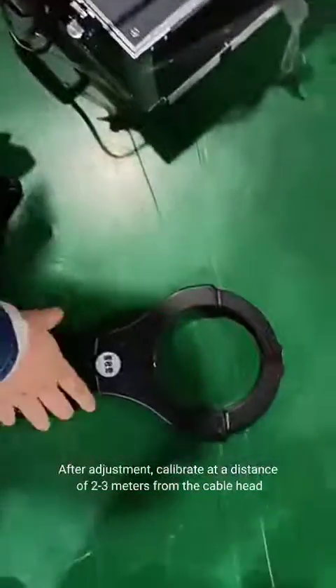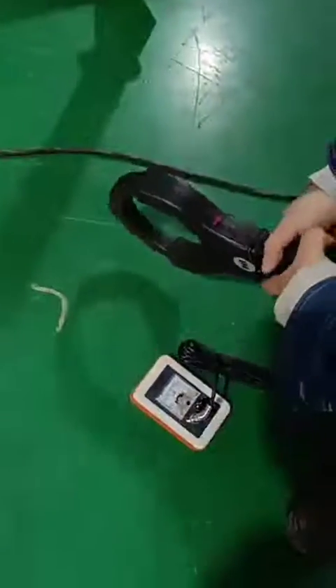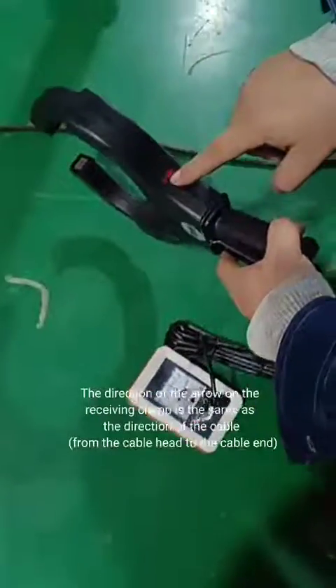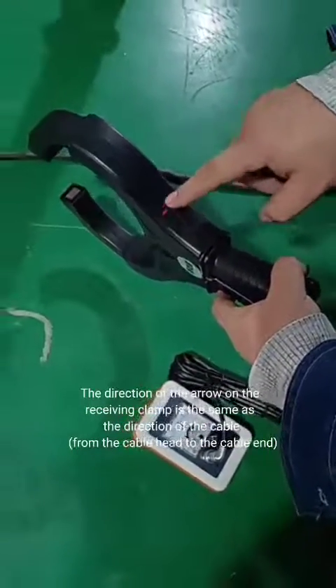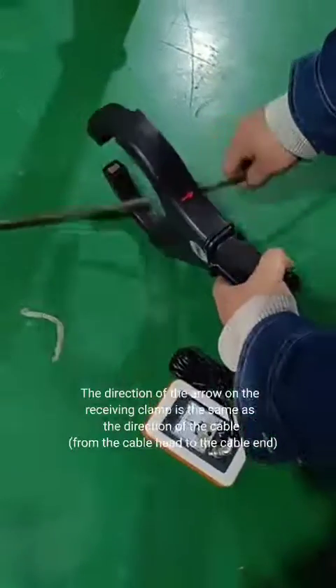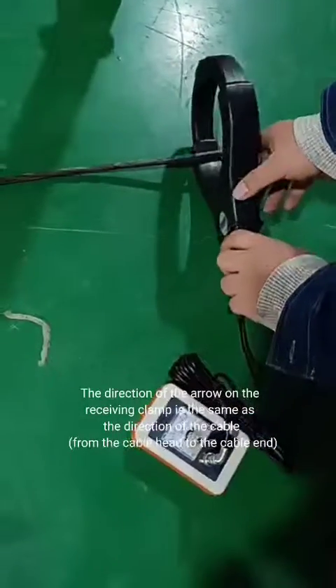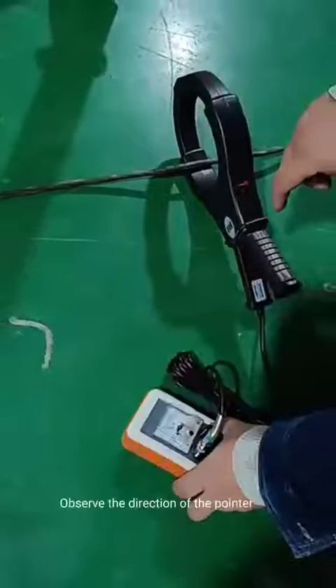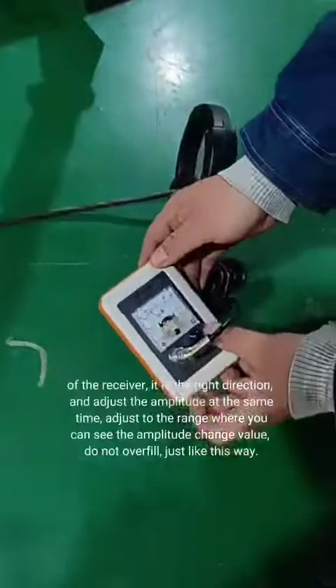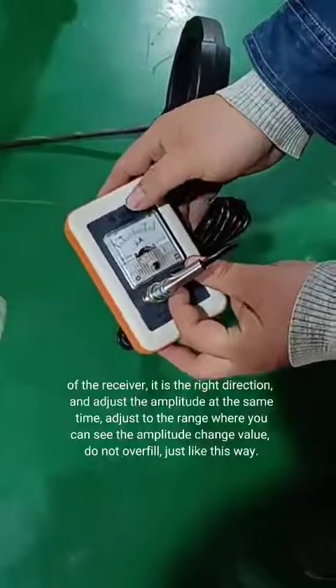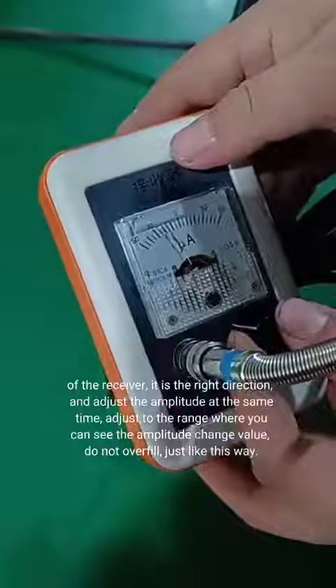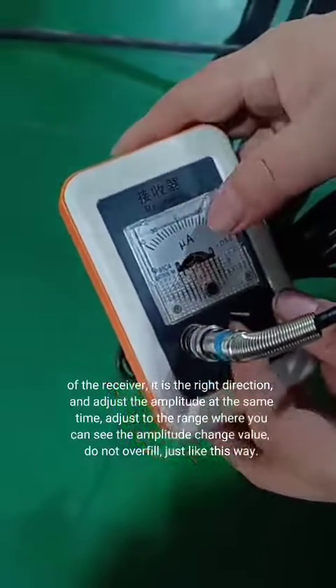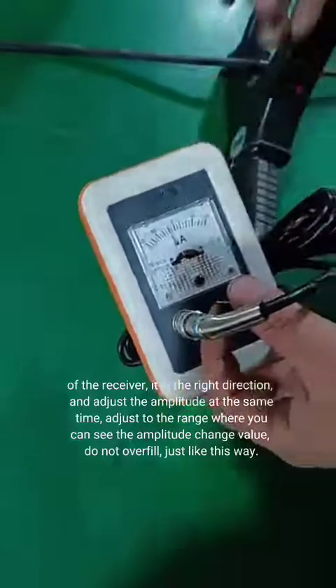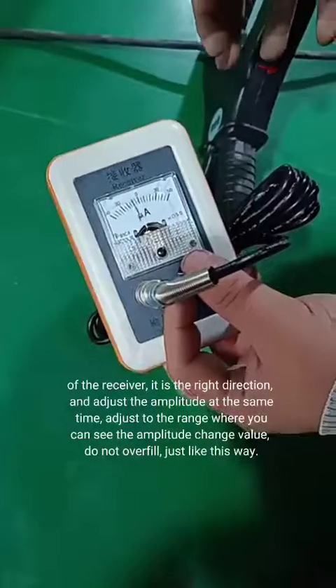After adjustment, calibrate at a distance of 2 to 3 meters from the cable head. The direction of the arrow on the receiving clamp is the same as the direction of the cable from the cable head to the cable end. Observe the direction of the pointer of the receiver. It is the right direction, and adjust the amplitude at the same time. Adjust to the range where you can see the amplitude change value. Do not overfill, just like this way.